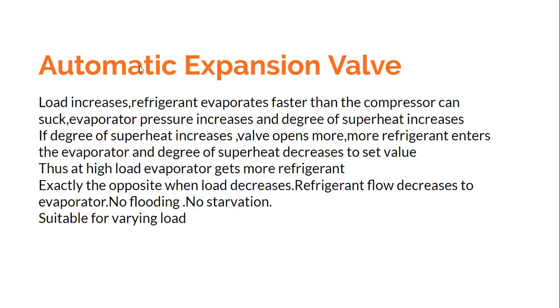Here, with an increase in the load, the refrigerant would evaporate faster, and the degree of superheat would increase. If the degree of superheat increases, the valve would open more, and that is what is required. So what should happen is, if the load increases, the valve should open more. What happens in the automatic expansion valve? When the load increases, the valve opens less. In the thermostatic expansion valve, when the load increases, the valve opens more. When the valve opens more, the refrigerant flow increases.